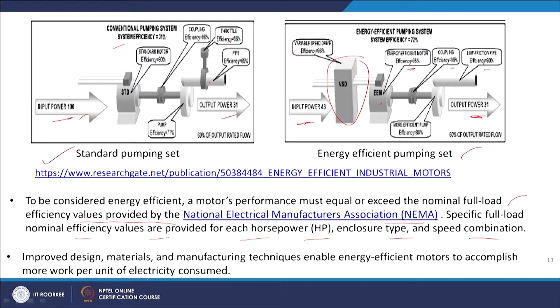To be considered energy efficient, a motor's performance must equal or exceed the nominal full load efficiency values provided by the National Electrical Manufacturers Association. They have given a list; specific full load nominal efficiency values are provided for each horsepower, enclosure type and speed combination. By comparing that we can tell whether it is energy efficient or not. Improved design, materials and manufacturing techniques enable energy efficient motors to accomplish more work per unit of electricity consumed, which we have discussed. Now, some energy conservation devices we will see.